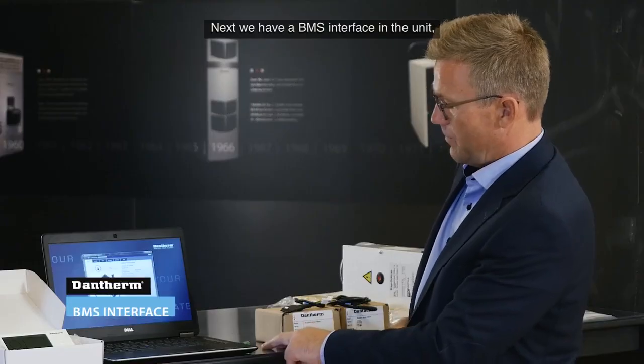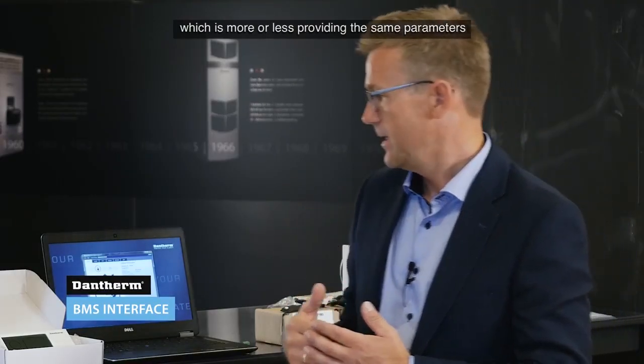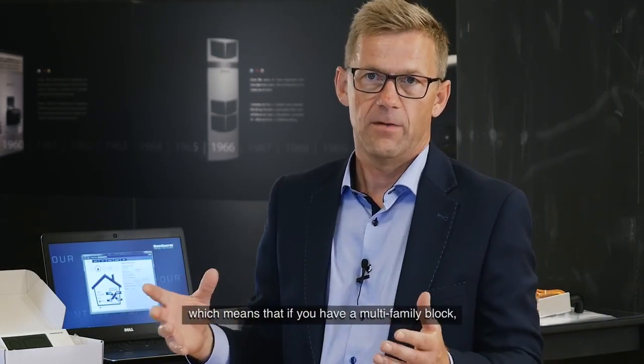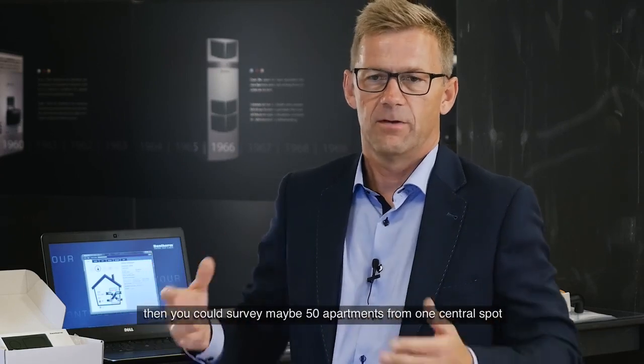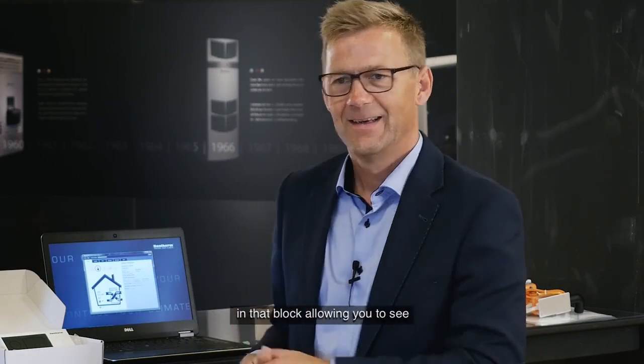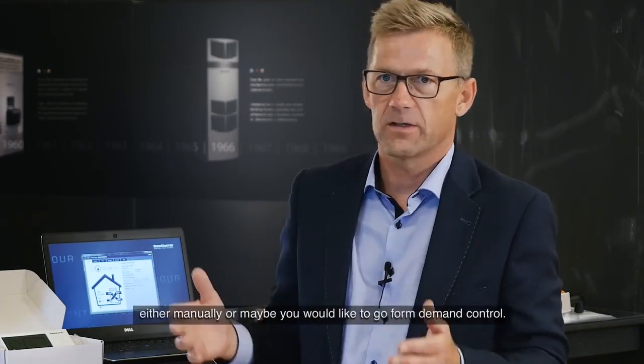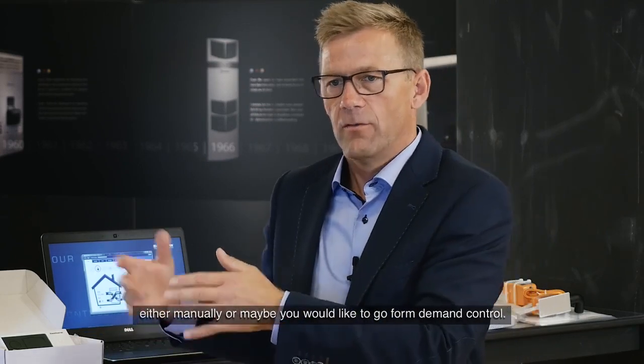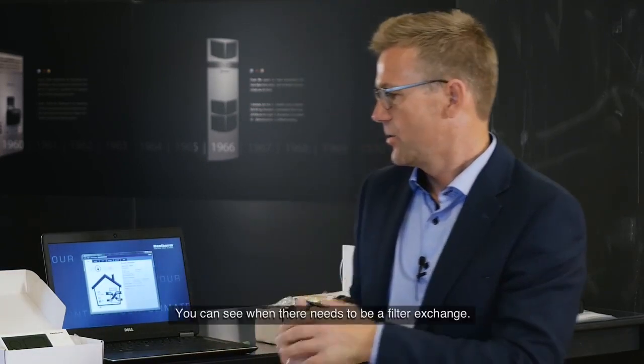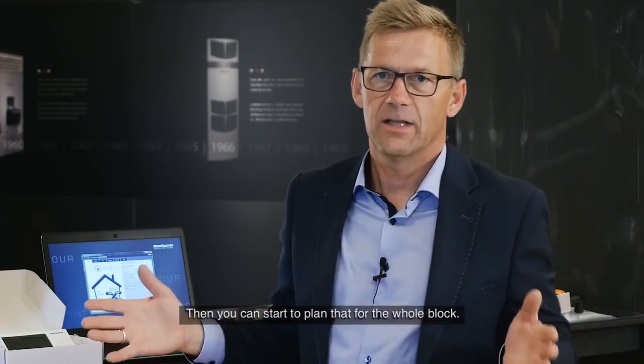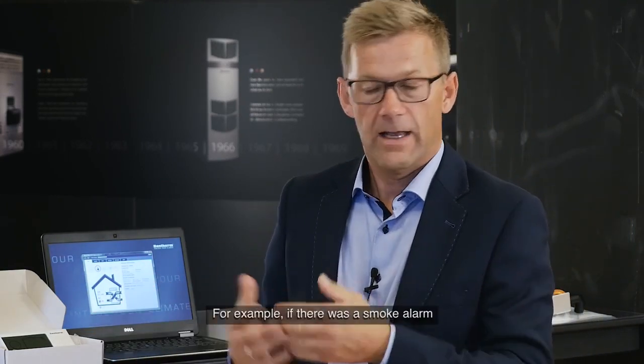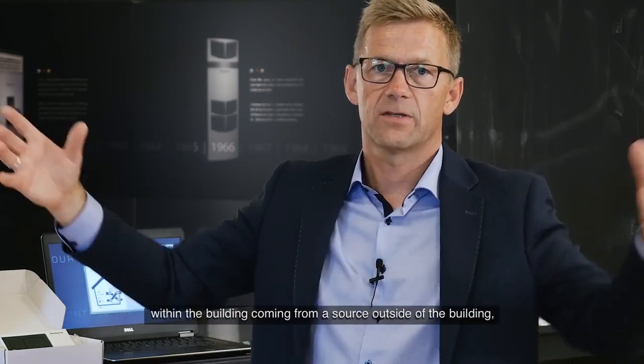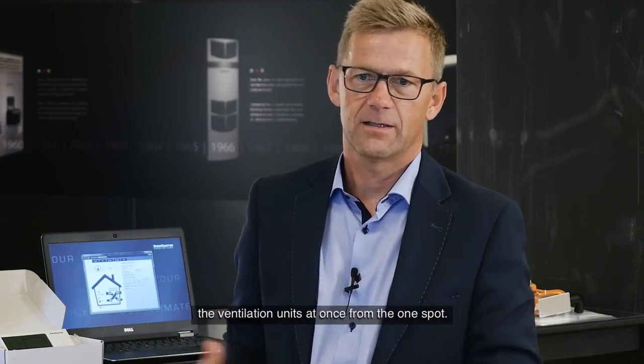Next, we also have a BMS interface in the unit, which has more or less the same parameters as the PC tool, meaning that if you have a multi-family block, you could survey, for example, 50 apartments from one central spot in that block, and then you could see possible alarms. You could decide how to run the units, for example, manually or from demand control. And you could also see when there's a need for filter exchange, and then start to plan that in the whole block. Also, for example, if there is a smoke alarm from the outside, the central person could shut down all the ventilation units at one spot.